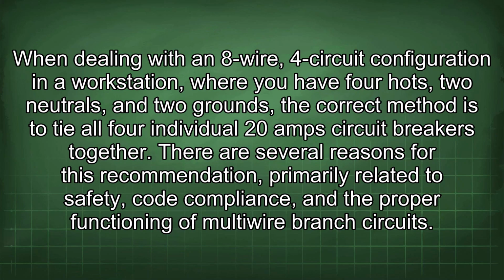When dealing with an 8-wire, 4-circuit configuration in a workstation, where you have 4 hots, 2 neutrals, and 2 grounds, the correct method is to tie all 4 individual 20-amp circuit breakers together.